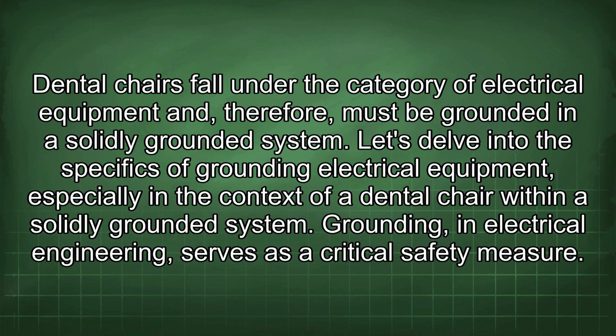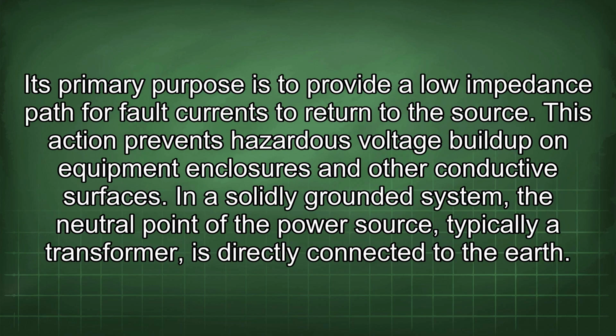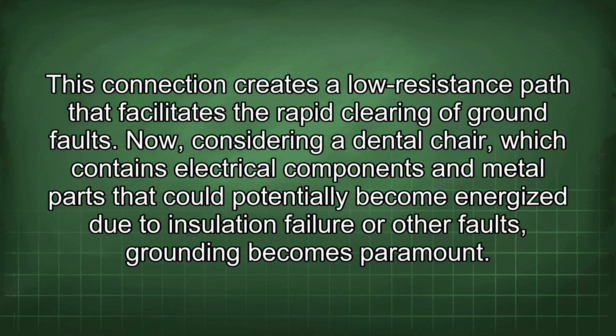Let's delve into the specifics of grounding electrical equipment, especially in the context of a dental chair within a solidly grounded system. Grounding in electrical engineering serves as a critical safety measure. Its primary purpose is to provide a low impedance path for fault currents to return to the source. This action prevents hazardous voltage buildup on equipment enclosures and other conductive surfaces. In a solidly grounded system, the neutral point of the power source, typically a transformer, is directly connected to the earth. This connection creates a low resistance path that facilitates the rapid clearing of ground faults.